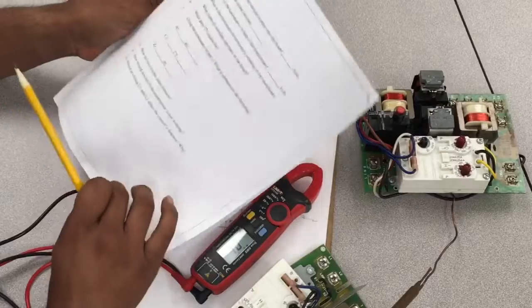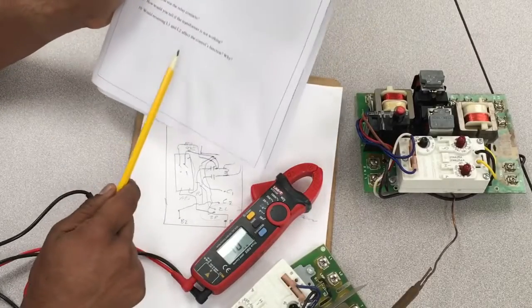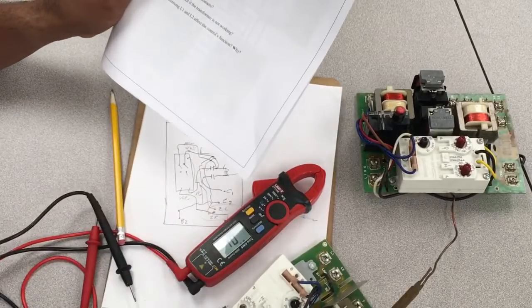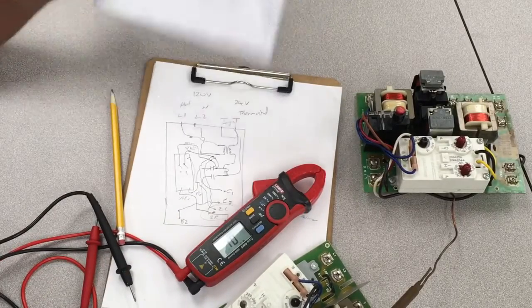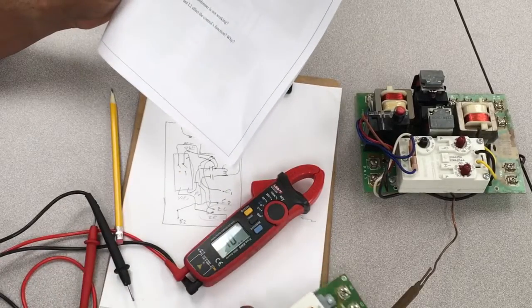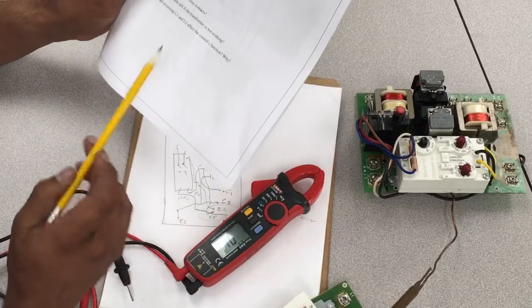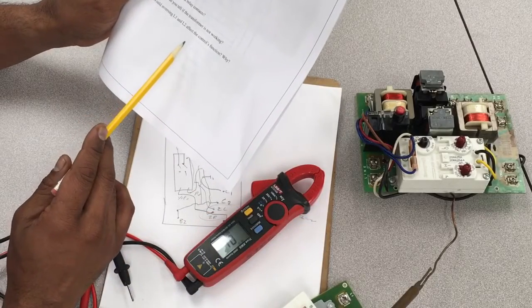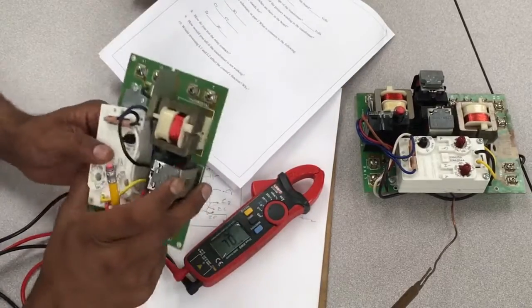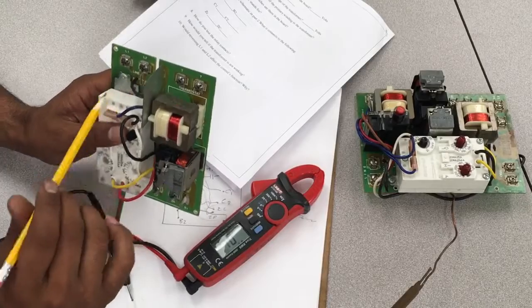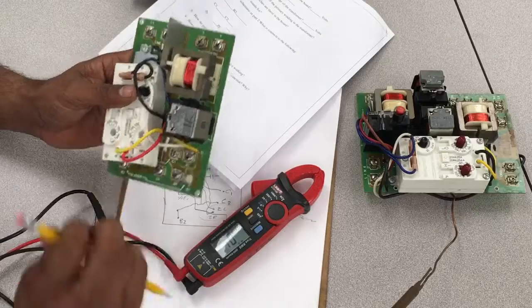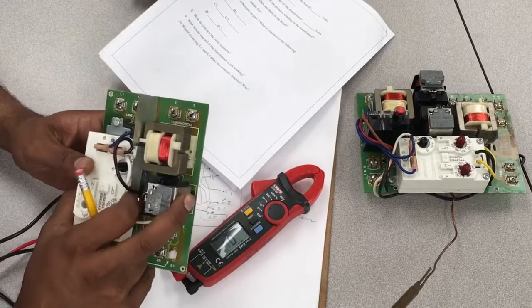Okay, how do you test the relay for the relay contacts? You basically do continuity and try to have this contact connected. This is very useful to do on these types of aquastats, but in other ones it's a little bit more tricky because they are solid state. Would reversing L1 and L2 affect the control function, and why? Thinking about that, I think it will pretty much affect the function, because that will reverse the entire operation of this aquastat, and that's a common mistake that happens when wiring an aquastat.